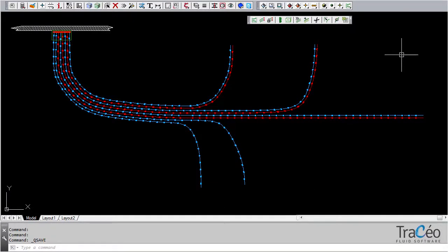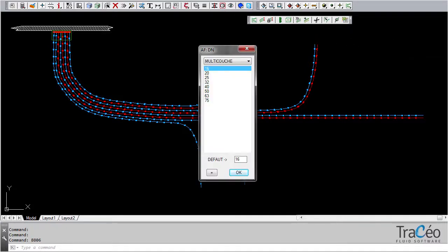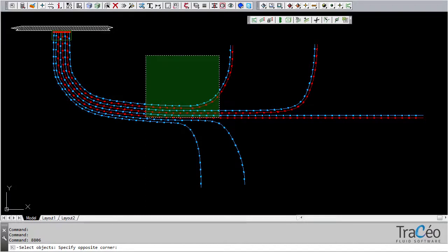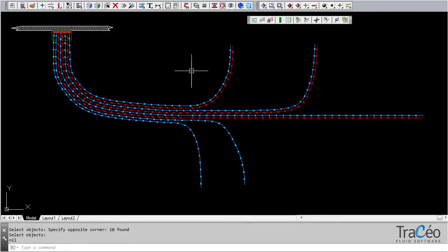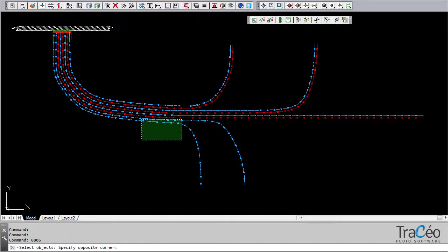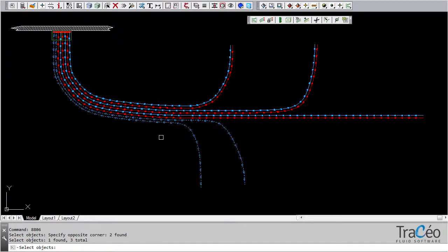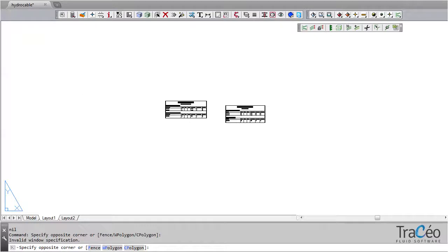Once the networks are drafted, we can indicate the diameters in order to generate a bill of materials. Choose the type of specification and the diameter. It's a DN25 for these ducts. Left click to select them, and then right click to validate the selection. Let's restart the command, choosing a DN20 for the two bottom ducts. Right click to validate. Let's start the bill of materials. It's available on AutoCAD as well as on Excel. Here we'll choose AutoCAD. And here is the result.